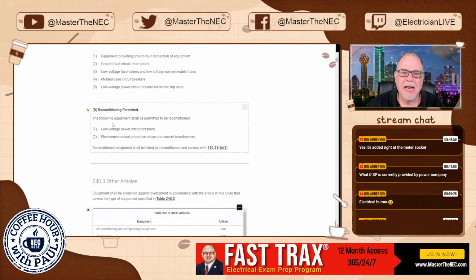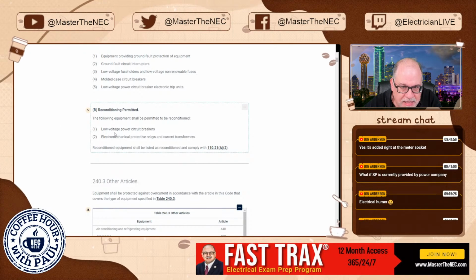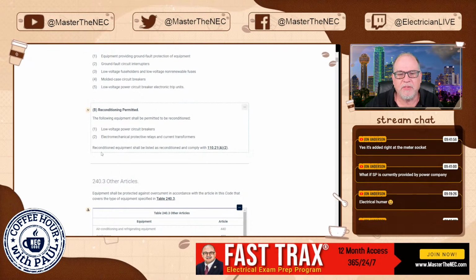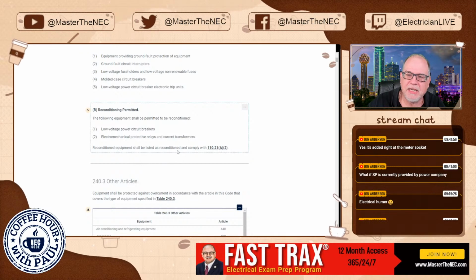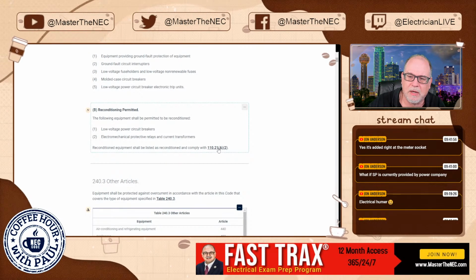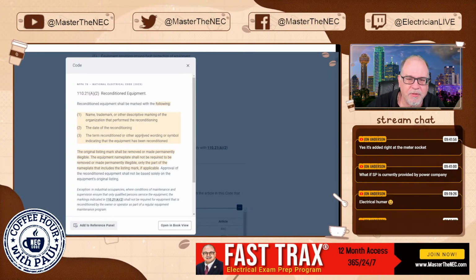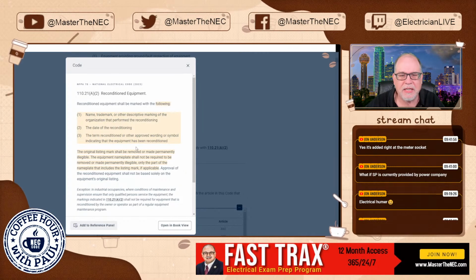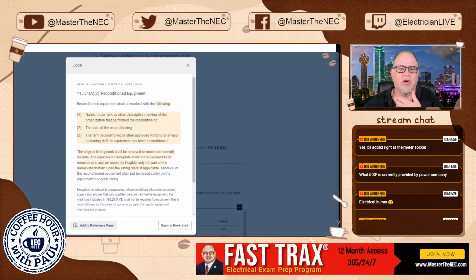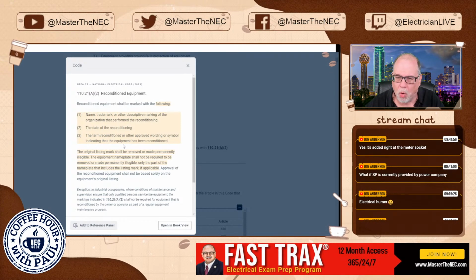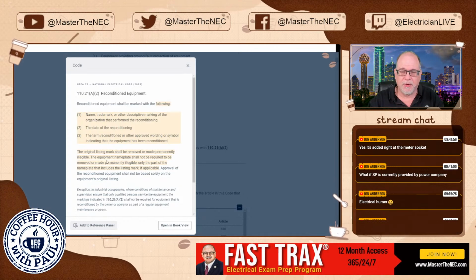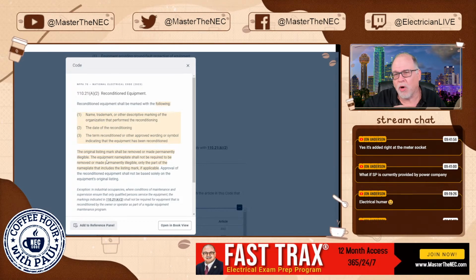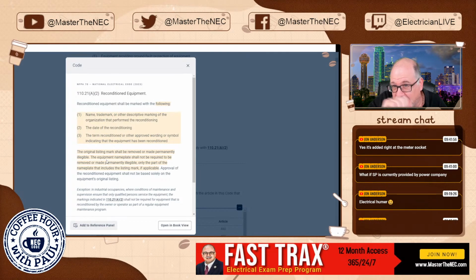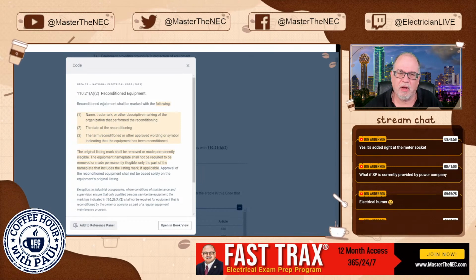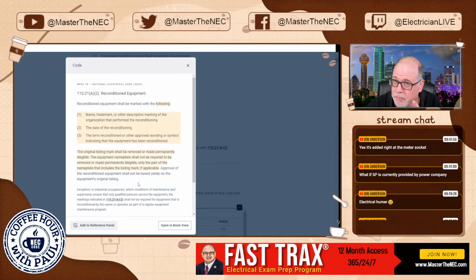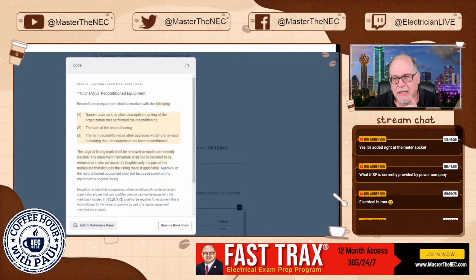All right, so now, if you're gonna recondition these, and it's a very limited list here when it comes to Article 240, it says the reconditioned equipment shall be listed as reconditioned and comply with 110.21(A)(2), and that is the marking from the manufacturer or whoever did the reconditioning, the date of that reconditioning. They have to put the term reconditioned or other approved wording or symbols on the piece of equipment. The original marking from the original listing has to be removed or permanently made illegible, means you can't read it. So again, see all that here? That's a change. We're going to be covering all those in an upcoming episode when we look at 100 and 110, but good sneak peek.